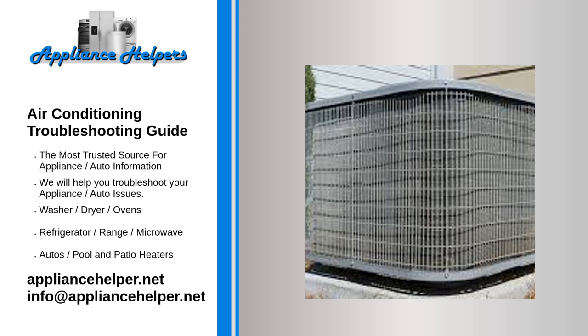Condenser problems will heat things up. When drawing up an air conditioning troubleshooting plan, don't forget to look at the condenser coil. The condenser has an important job to do. It is responsible for discharging the heat removed from the air by releasing it outside of the building. The condenser coil is part of your outdoor unit, which means it's exposed to dirt, soot, and assorted pollutants that make it grimy. If the coils are dirty, it will interfere with the transfer of heat, make your unit work harder, and add to the wear and tear on your system.